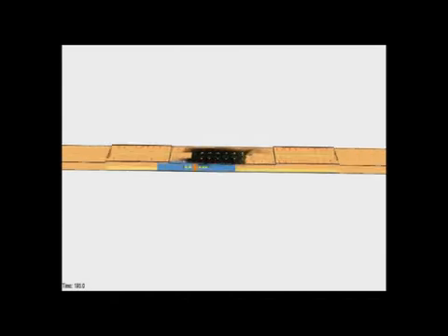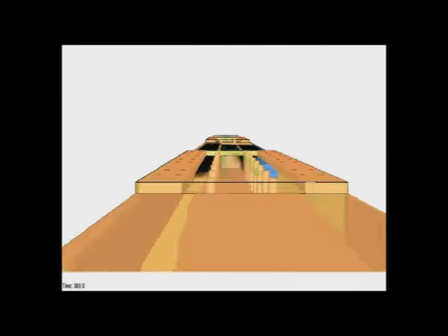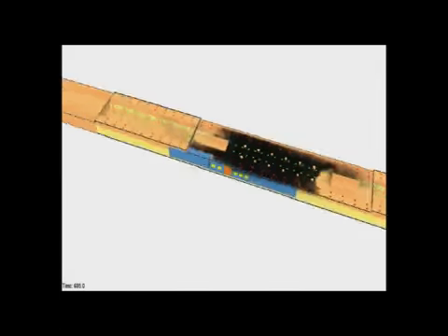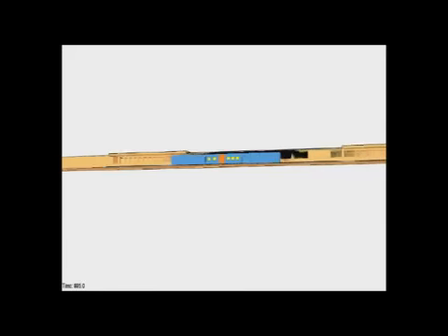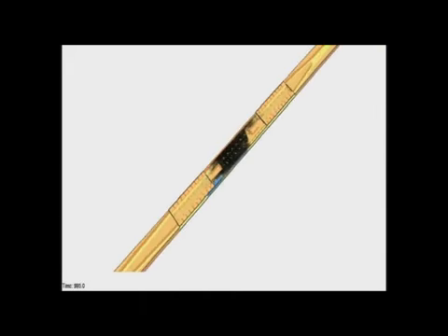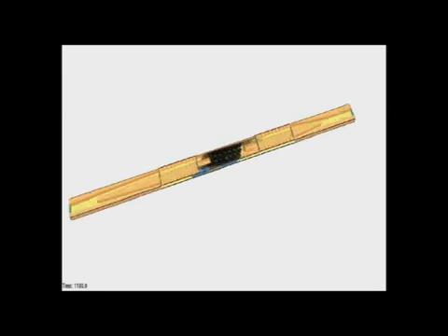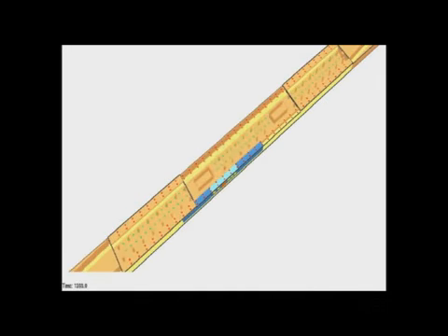We came up with this design and we did the simulation. In the simulation we could see that the visualization is much faster. It's already 300 seconds. You can see that this whole area was covered in smoke, and there was almost zero visibility in this area. So people would be trapped here because of this. So this case was obviously not approved.